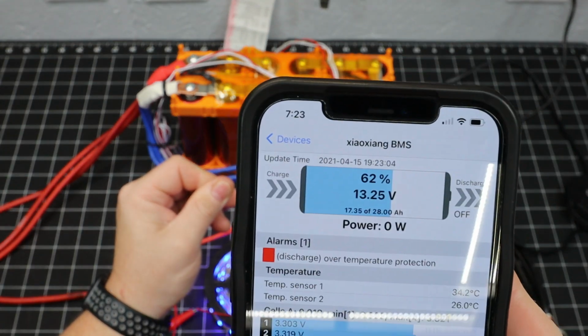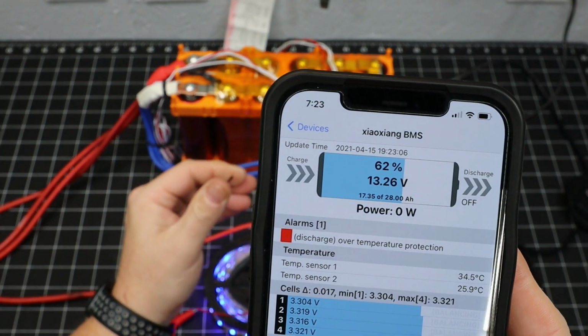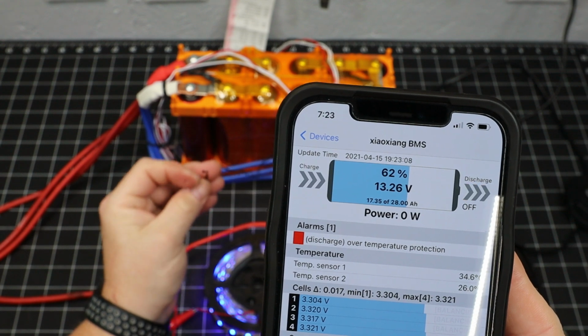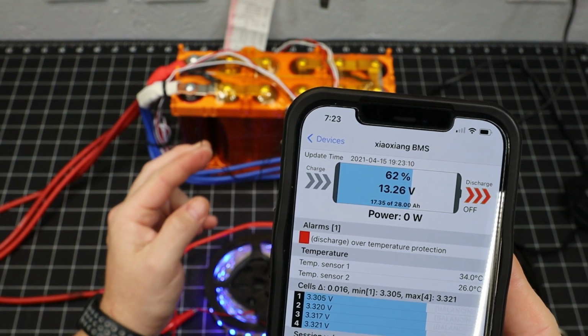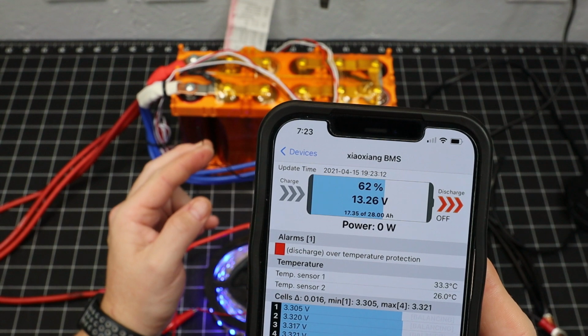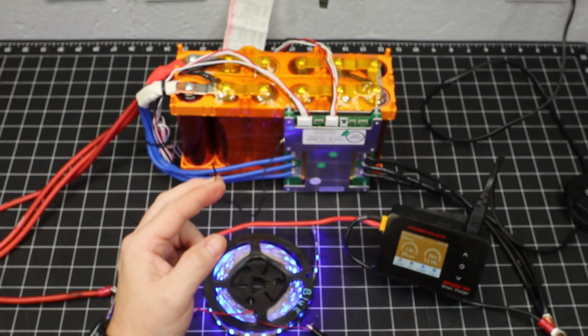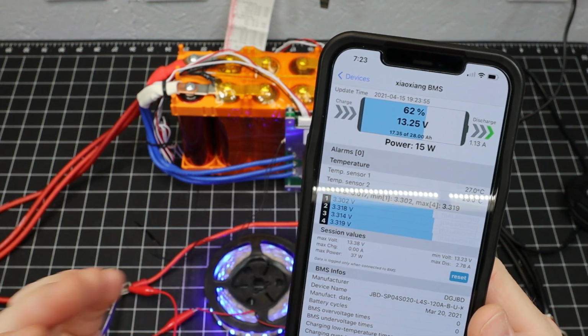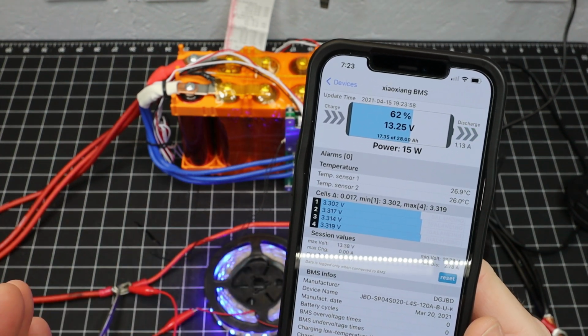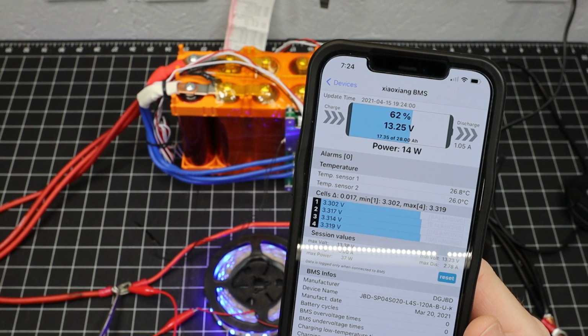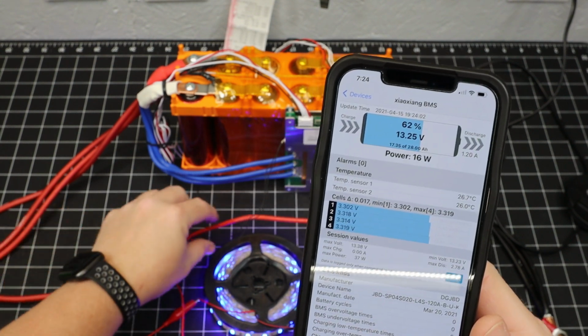So there we got a discharge over-temperature protection, and I got it set to 32 degrees Celsius. Okay, so that is great. I've made some setting changes so that when it gets above 30, it'll cut off and restore at 29.